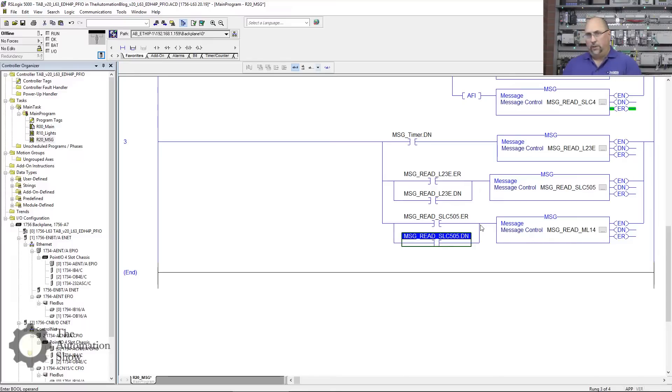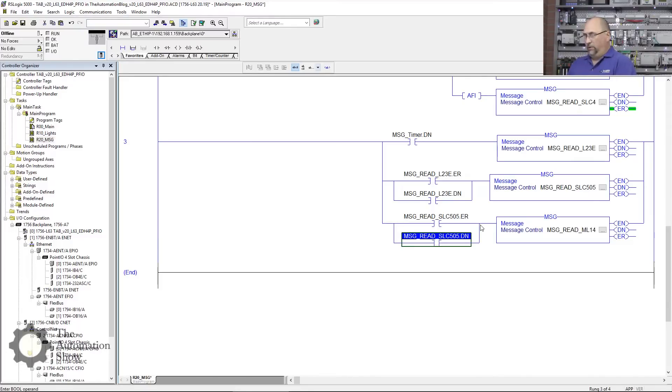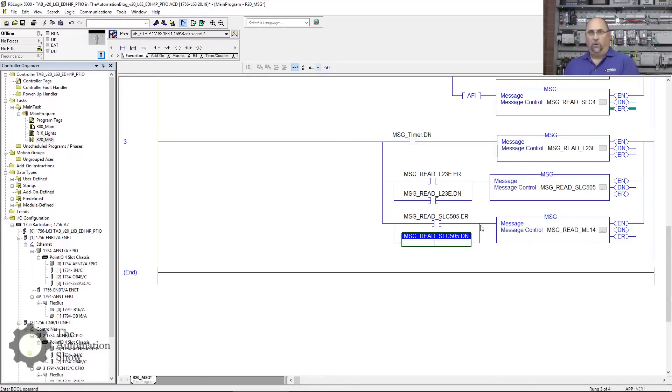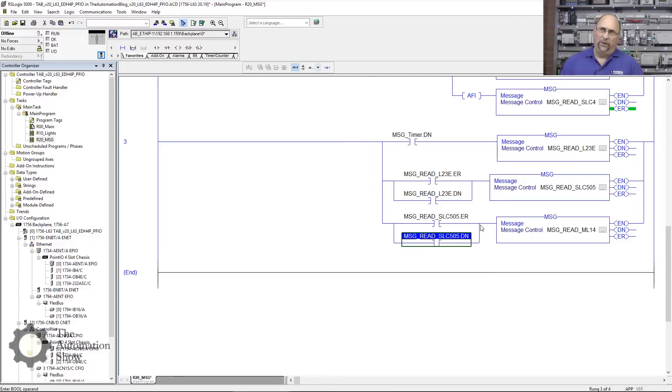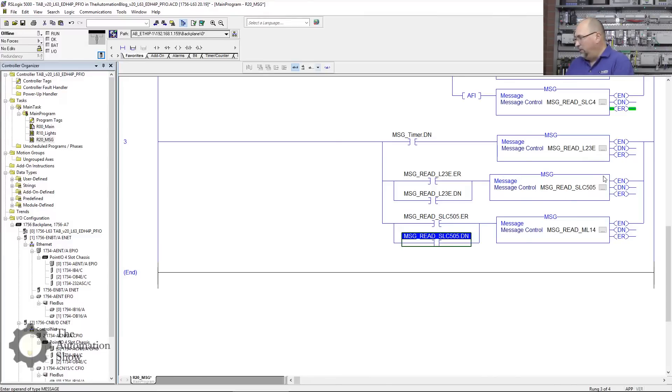Now the only downside of doing this interlocking, as I mentioned in previous episodes, is if you have long timeouts, because then it slows the round robin down. When you do this, a lot of times you'll reduce your timeouts. If it doesn't reply in a reasonable amount of time, you say forget it, it's not there, or we got some noise, we're just moving on. That's really an effect you see a lot on very slow serial networks where that becomes an issue, but not many people use those anymore.